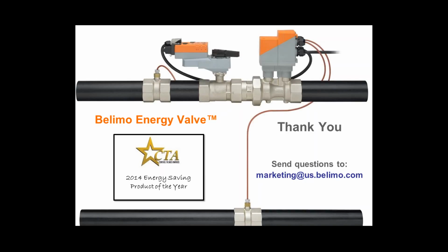You can write a routine such that the automation system will disable delta T manager under certain circumstances that you would outline. As I said, the PICS statement is in that tech document if you want to take a closer look. Basically, you can see the supply and return water temperatures, the flow, and the BTU production, but you can also see and command the delta T set point and enabling or disabling delta T manager altogether.